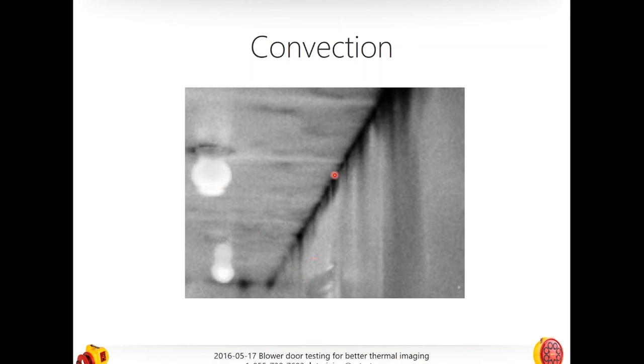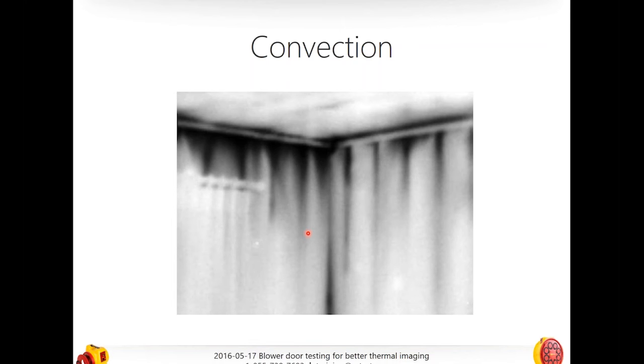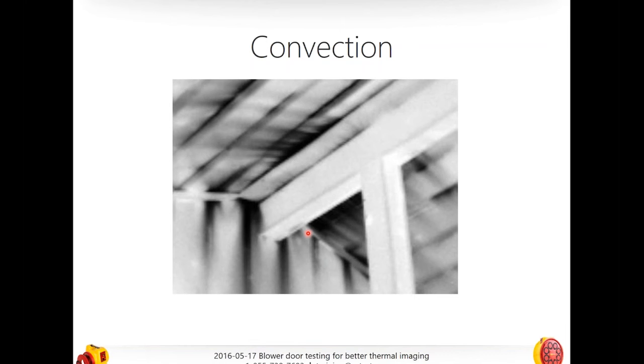Here's a more profound example. On one side we have an outside wall with windows; on the other side is an interior hallway with two lights — and the blower door is running. Both show obvious leakage. We're looking at open top plates — one exterior, one interior. Convection makes it so that it doesn't make that big of a difference; in fact, the interior one might even be worse.